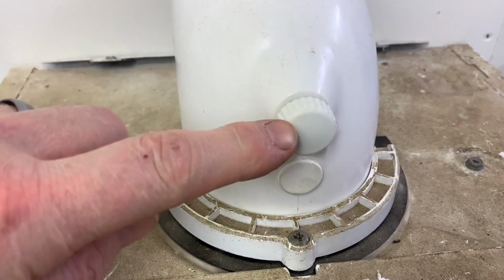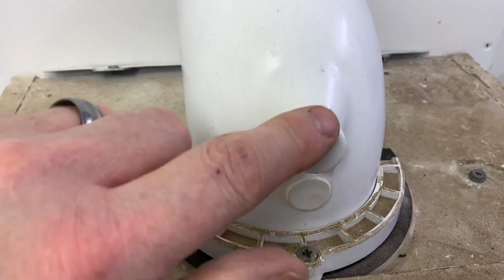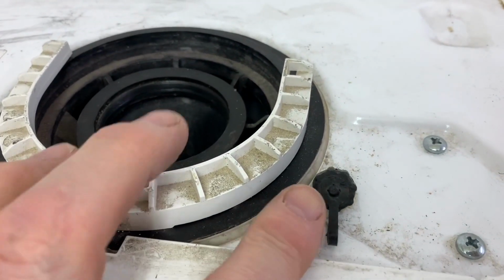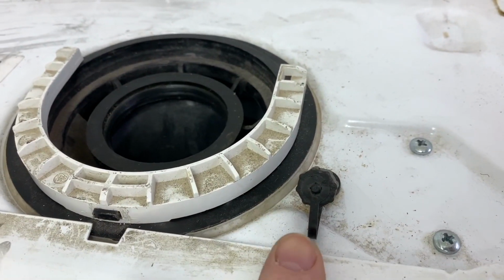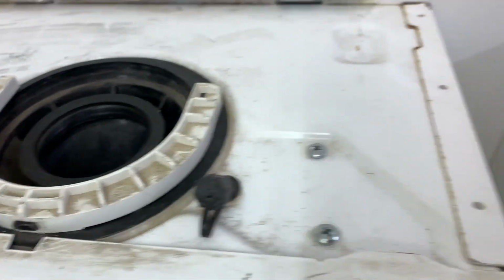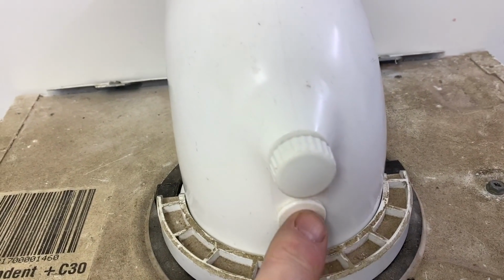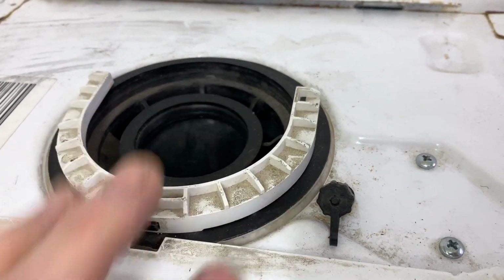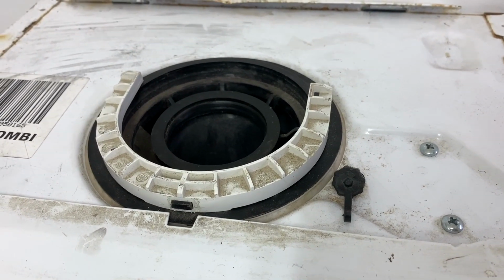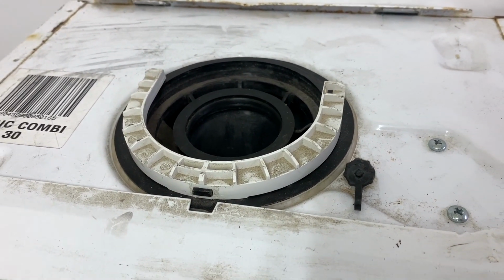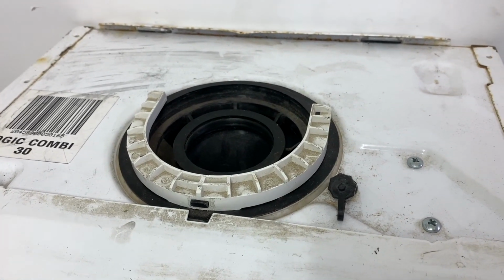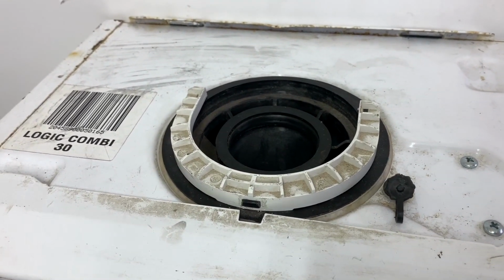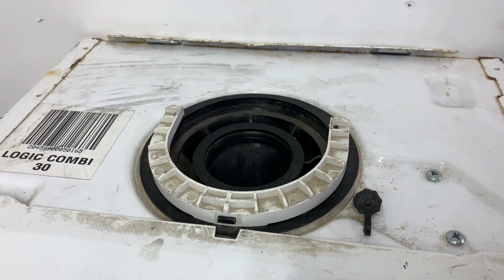Next changes, in the newer version, the sample points are now in the flue. But in the older version, this is the sample point for your flue gas analysing. No integrity testing. So you could do integrity here on the newer version, but on the older one, there was only one flue gas analyzer sample point. You also couldn't put these in high and low really easy neither, whereas the new boilers you can. So that's pretty much the top.